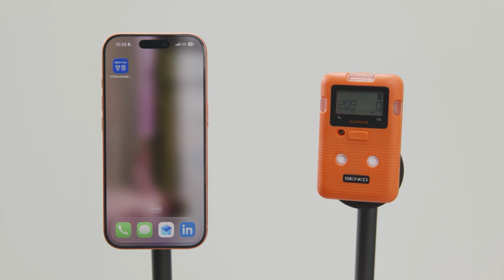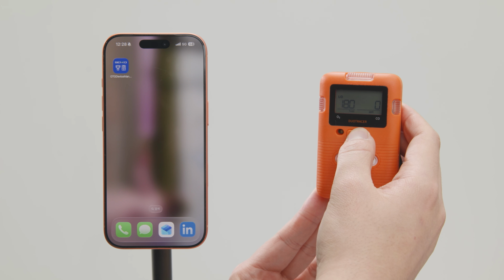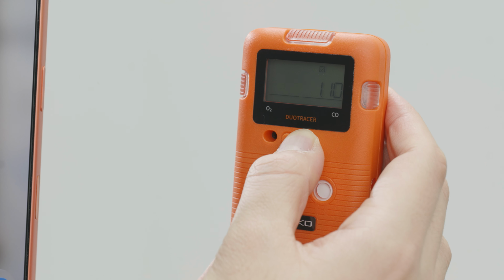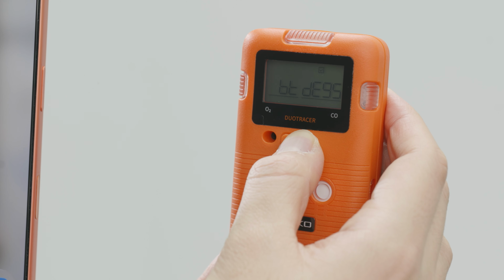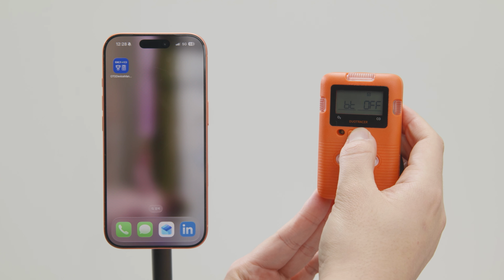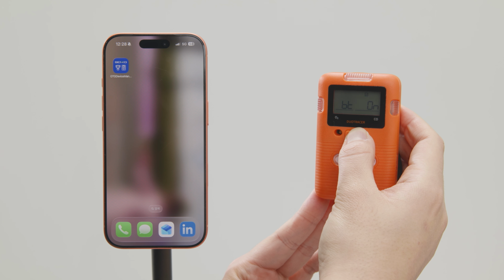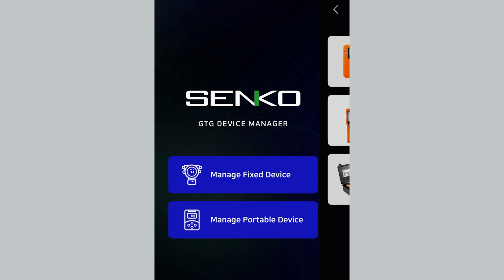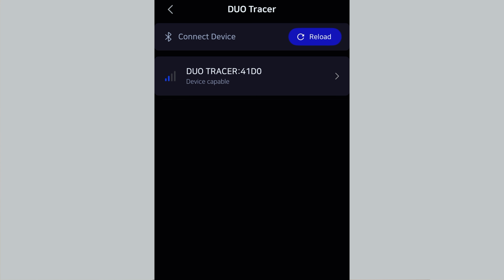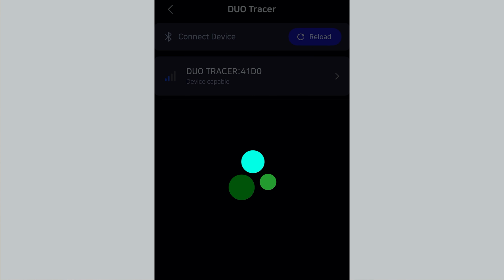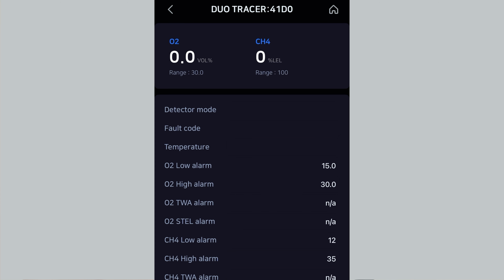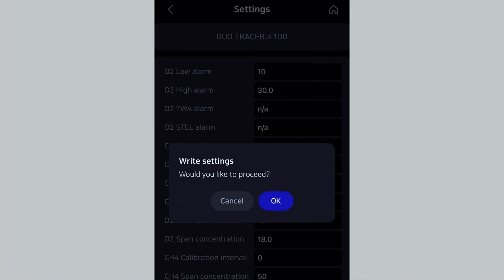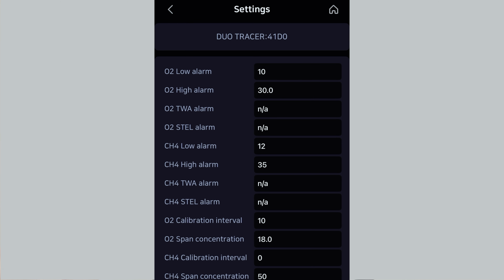Another key feature that really sets Duo Tracer apart is its wireless capability. Once you activate the wireless function on Duo Tracer, by connecting it to the Senko app, you can check the device status at a glance, including real-time gas readings, alarm status, and battery level, all without having to operate the device directly. On top of that, you can change device settings right from your mobile device. Measurement data collected in the field can also be sent immediately via email or SNS, making it easy to store, share, and analyze the information.